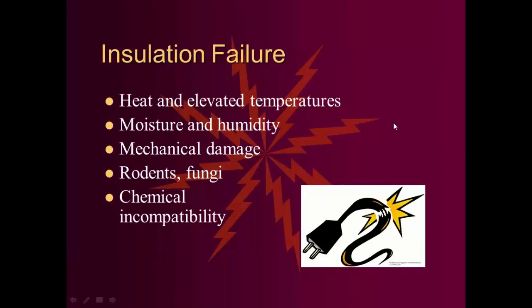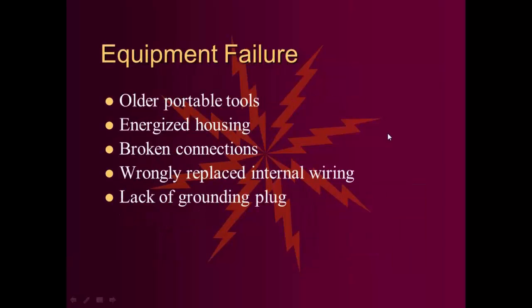When you're pulling wire into a piece of equipment, please clean up the wire pulling lubricant, because if it makes contact between a live terminal and the casing, when it's energized, it's conductive and it will blow up. Okay? Just a word to the wise there. Chemical incompatibility, two dissimilar metals, these are all different things that wind up creating a problem for us. Older portable tools, energized housings. Remember, if there's no path back, the equipment remains energized and you come up and touch it, you are now the path back. And milliamps is all it takes, right? Broken connections, arcing faults, wrongly placed internal wiring, lack of a grounding plug.